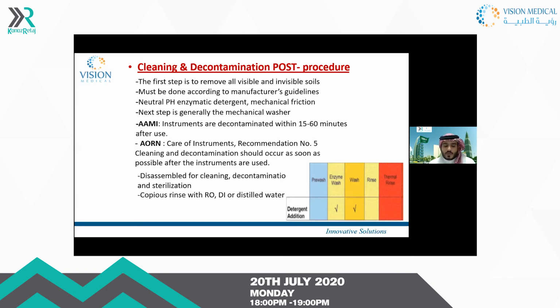Also, disassembling is the most important thing. As we know, most of us here work in CSSD, so the most common problem we face is disassembling. This is disassembling for cleaning, decontamination, and sterilization in CSSD, starting from day 1 when you receive the instruments. Everybody in the department, or the end user in the other department, should know after use how to disassemble the instrument and send it to CSSD. So we will not sterilize or clean it before we make sure it's disassembled. Copious rinse with RO and deionized or distilled water.